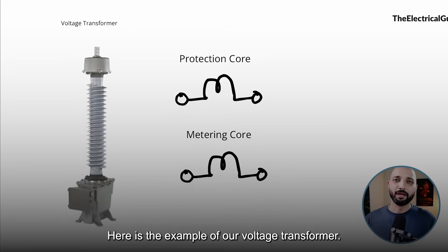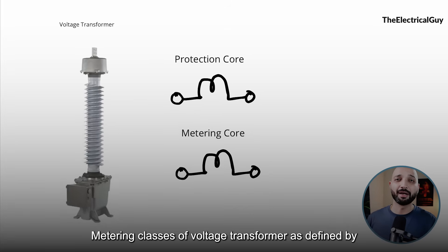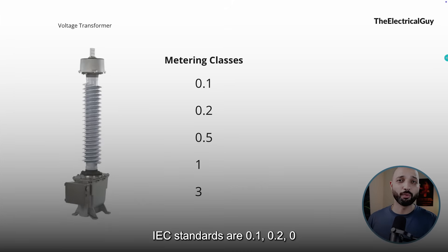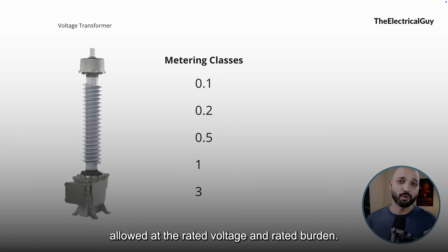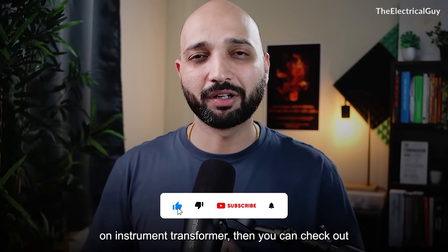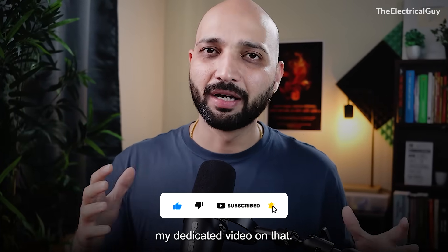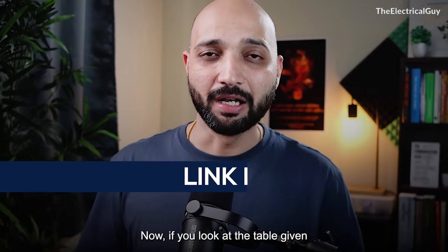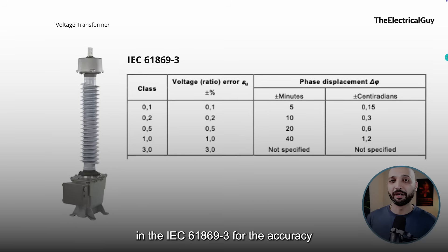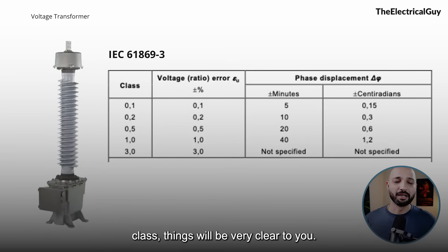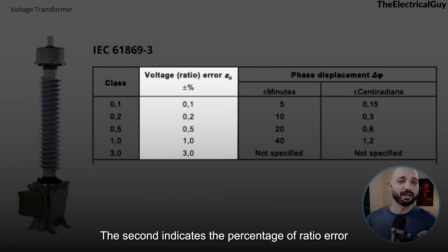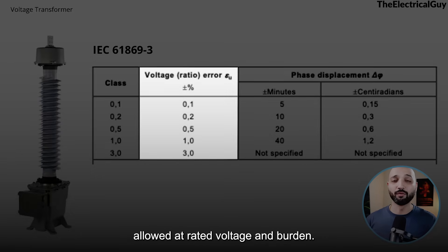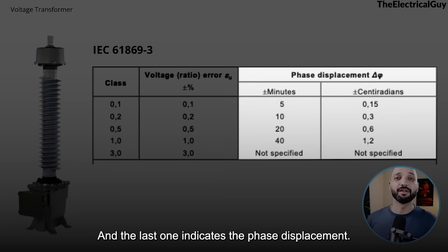Here is an example for the voltage transformer. The metering classes of voltage transformers as defined by IEC standards are 0.1, 0.2, 0.5, 1, and 3. This basically indicates the percentage of ratio error allowed at the rated voltage and rated burden. If you look at the table in IEC 61869-3 for accuracy classes, things become very clear. The first column indicates the class name, the second indicates the percentage of ratio error allowed at rated voltage and burden, and the last column indicates the phase displacement.